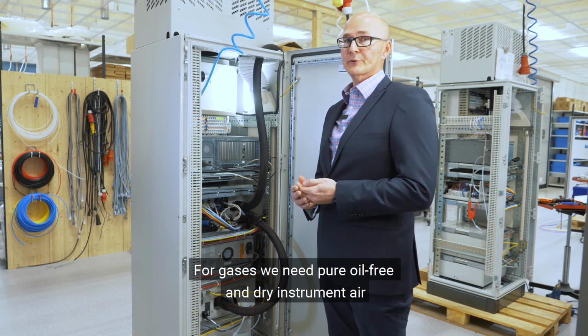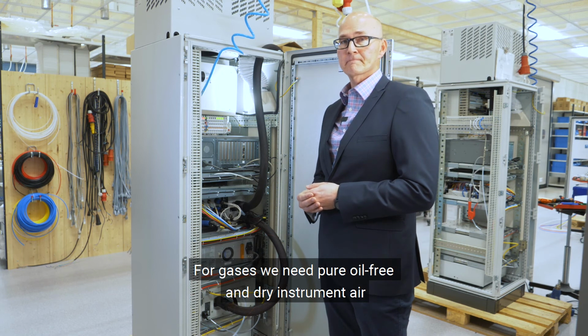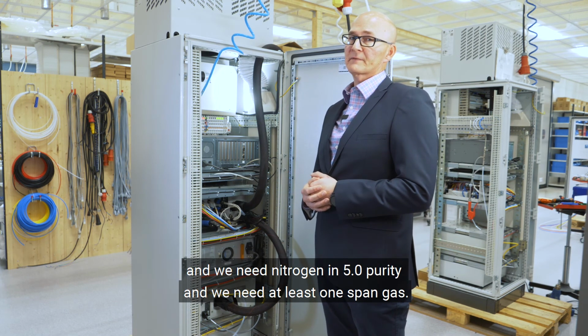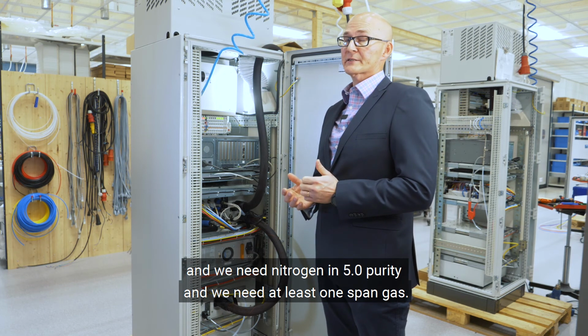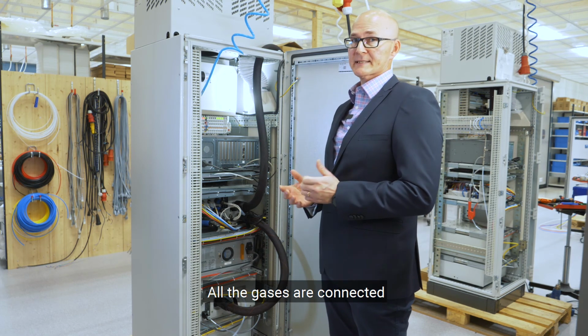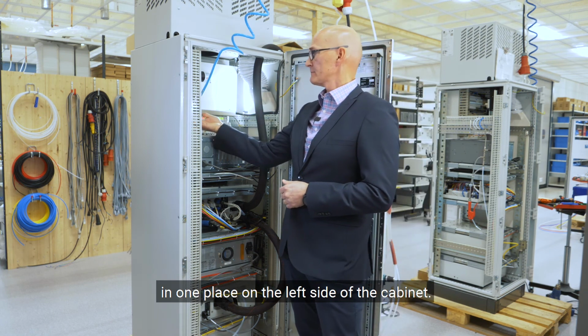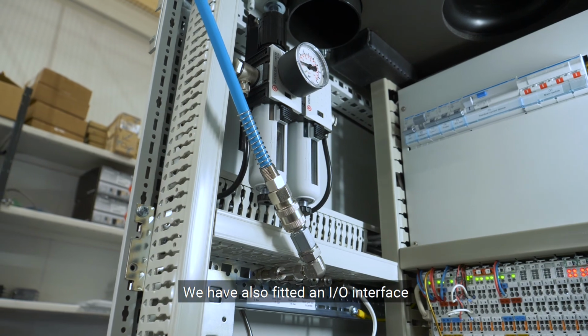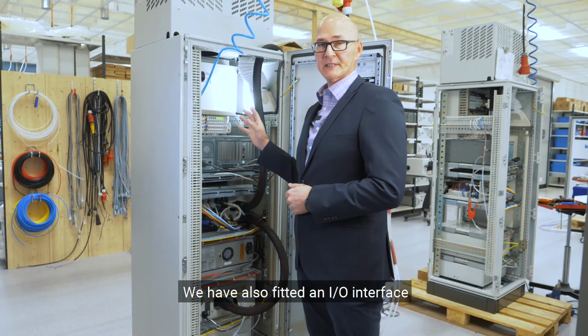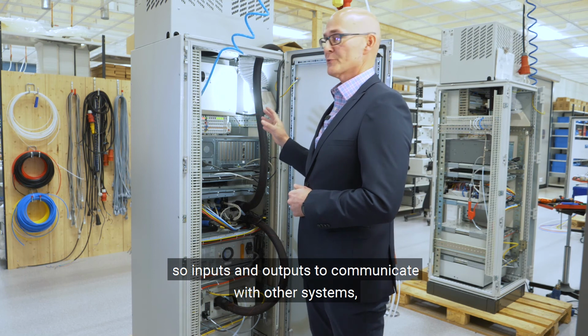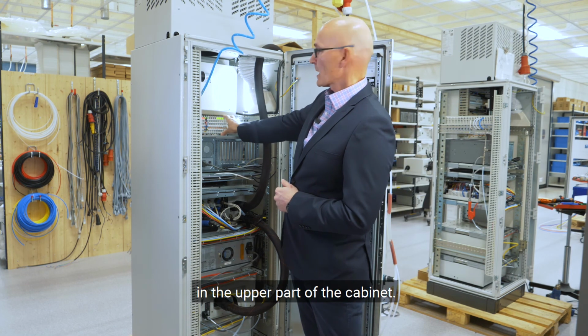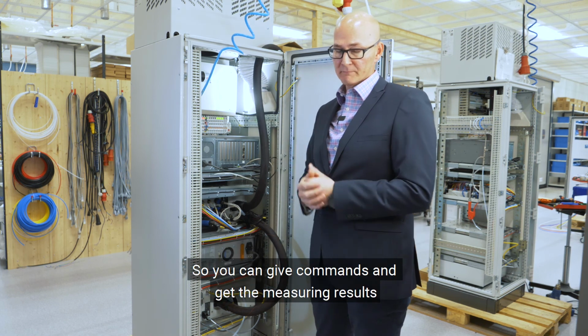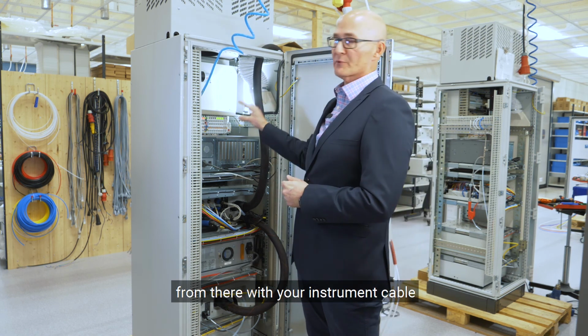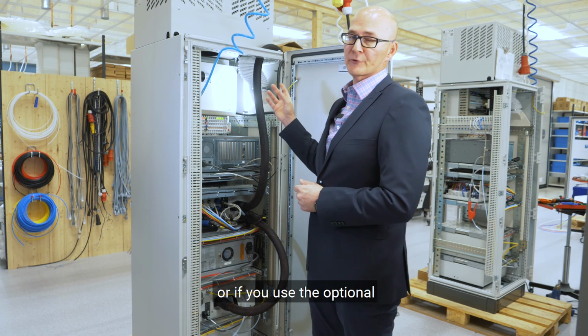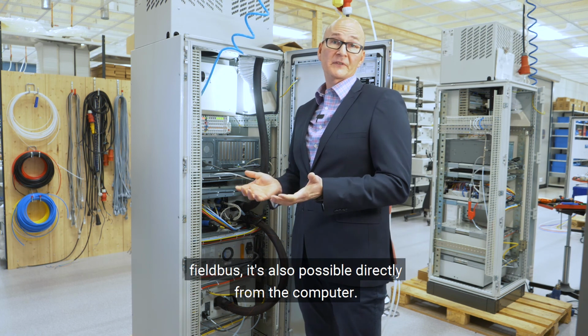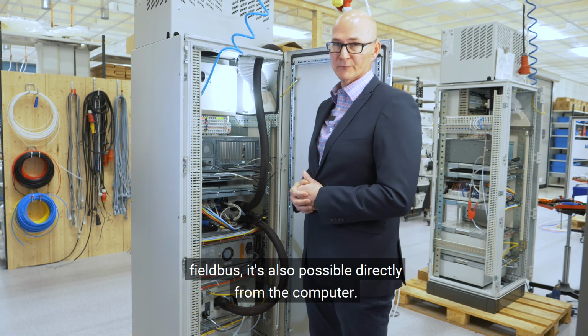For gases, we need pure, oil-free and dry instrument air, and we need nitrogen in 5.0 purity, and we need at least one span gas. All the gases are connected in one place on the left side of the cabinet. We have also fitted an I/O interface, so inputs and outputs, to communicate with other systems in the upper part of the cabinet. So you can give commands and get the measuring results from there with your instrument cable. Or if you use the optional field bus, it's also possible directly from the computer then.